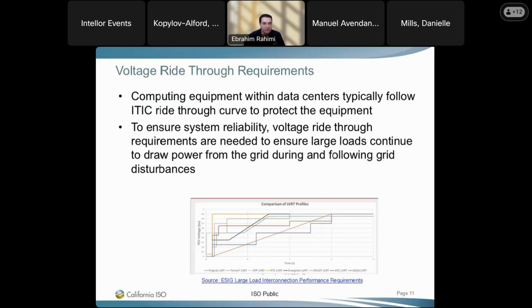Voltage ride-through requirement is one major topic in many jurisdictions. We know that computing equipment within a data center, at a basic level, follows an ITIC curve, a ride-through curve, to protect the equipment. However, when it comes to the transmission system and system reliability, voltage ride-through requirements are needed to ensure large load continues to draw power from the grid during and following typical grid disturbances. There's a link to a report by ESIG, and there are 8 different entities that each have their own voltage ride-through requirements, and as you can see, they're all different. We're not going through detail of those, but that shows it's not one size fits all - to maintain the balance between feasibility and reliability, the requirement could be slightly different for every system.